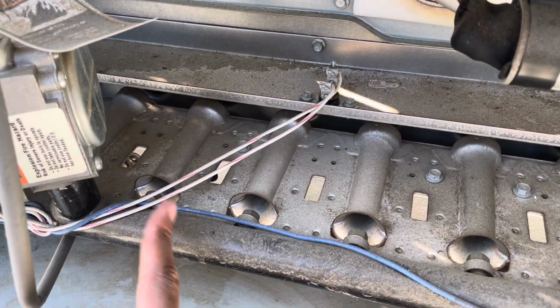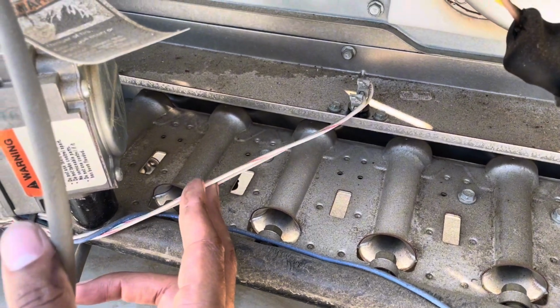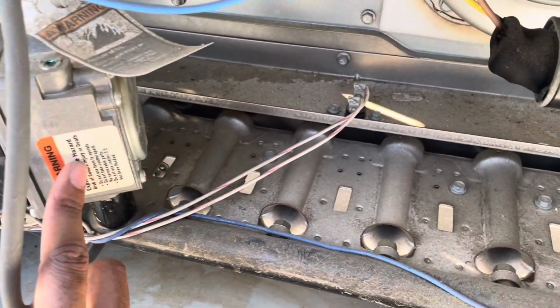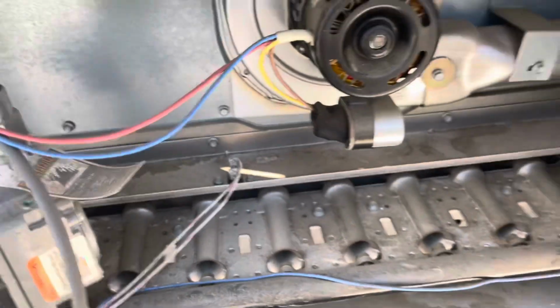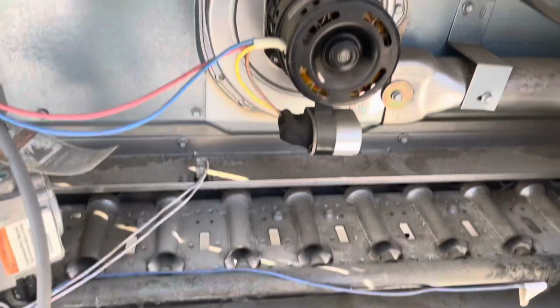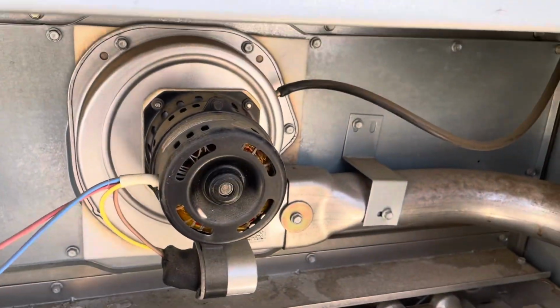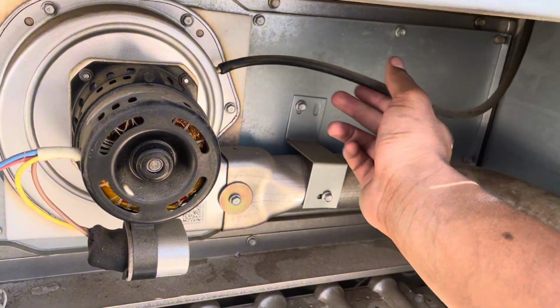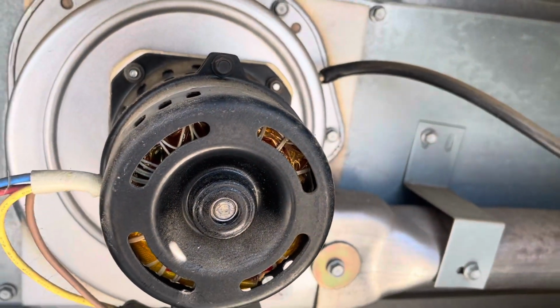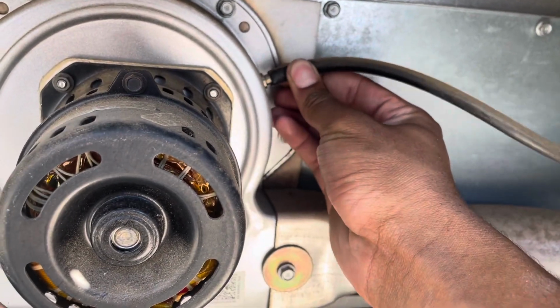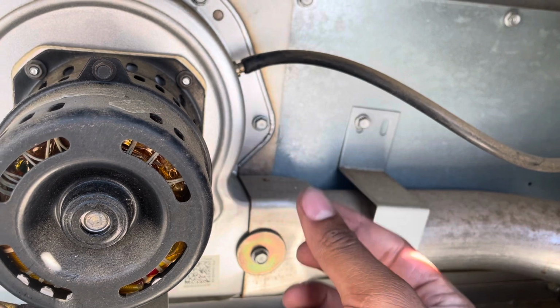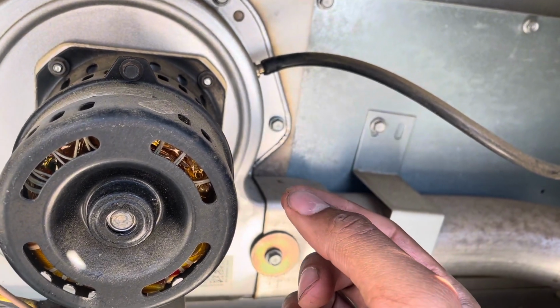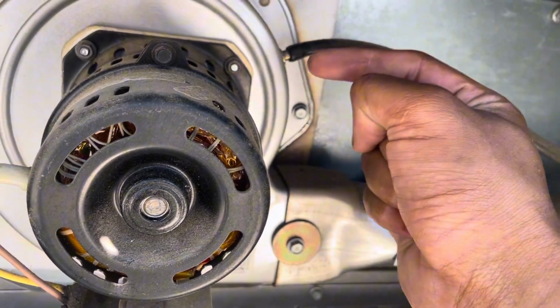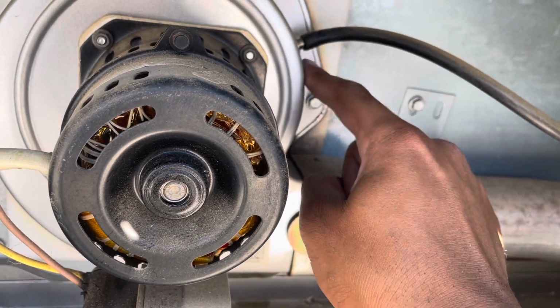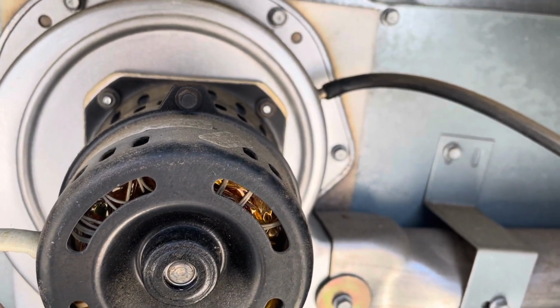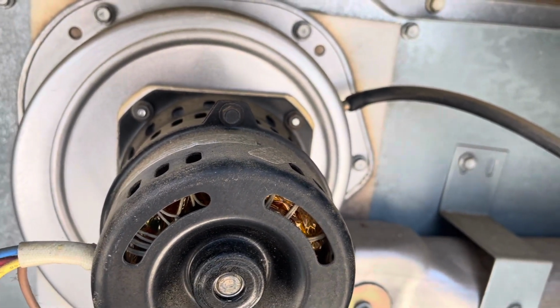You have your spark. Your igniter comes on, the gas valve opens up, energized by 24 volts, gas flows through the manifold, and the gas is ignited. All right, so yes, check your hose, make sure it's not torn or ripped, or that there are no tears along the way. Also, you can take this hose off, and take a piece of skinny wire, or something small and skinny, and stick it in the hole, because sometimes the hole can get plugged up, and that can prevent the switch from closing.